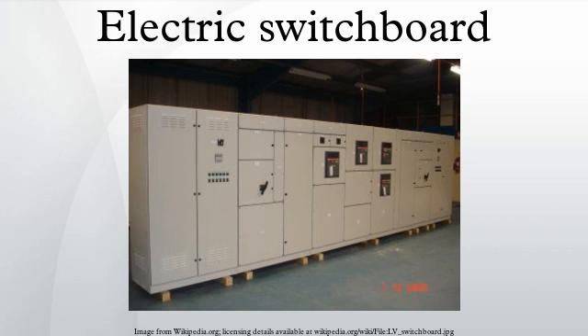There may also be controls for the supply of electricity to the switchboard, coming from a generator or bank of electrical generators, especially frequency control of AC power and load sharing controls, plus gauges showing frequency and perhaps a synchroscope. The amount of power going into a switchboard must always equal the power going out to the loads.